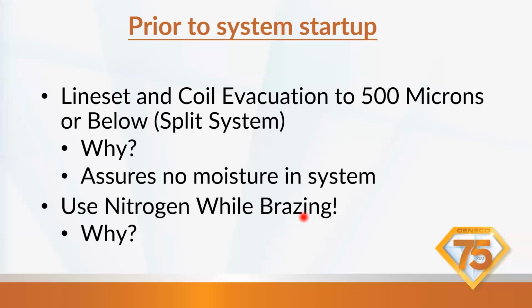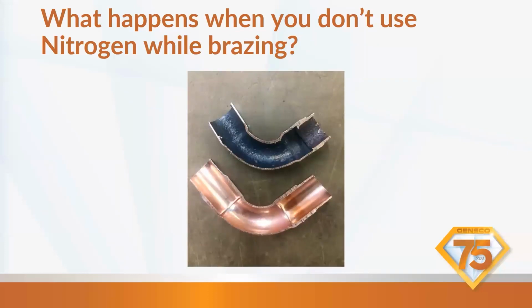And always use nitrogen while brazing. I can't stress that enough, because I like to show these slides. If you do not use nitrogen, you get all this oxidation on the inside of the pipe. That's the oxygen in there burning off. When you run nitrogen through, it eliminates the oxygen, so you do not get this oxidation. And then once the refrigerant enters in here, it just cleans that clean to look like this pipe. And where's all that go? Into the strainer and the EEVs and the TXVs. And then, boom, you have faulty metering devices that you got to repair. So just, again, stress to everybody, nitrogen when brazing eliminates this oxidation.